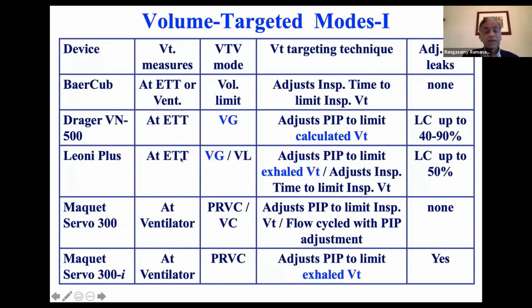Leoni Plus only measures at the endotracheal tube, and you can deliver volume guarantee mode or volume limited mode. And I'll show you the difference between volume guarantee versus volume limit or volume control. Here, they adjust the PIP to limit the exhale tidal volume. So they use exhale tidal volume. BaerCub uses inspiratory tidal volume. Servo 300 is flow cycled, with PIP adjustment and inspiratory tidal volume. So if you truly want to use volume guarantee mode or volume control mode, you should adjust your exhale tidal volume, not inhale tidal volume.